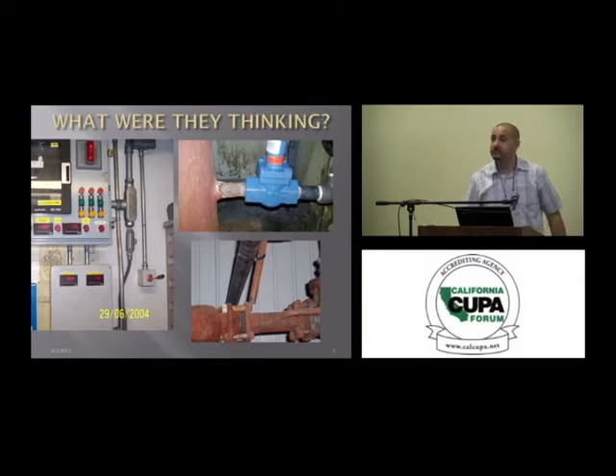Well, on that one valve, it was the new valve that was connected to that one line. It also looks like it's cross-threaded with something. I looked at it, and it's just the amount of corrosion that's causing that nipple to do that. It's just eaten up. I thought the same thing, so I came back with a sulfur stick and checked. There was no ammonia leak or anything.